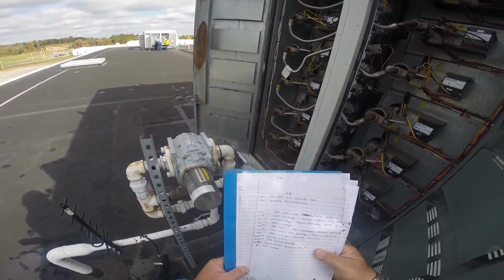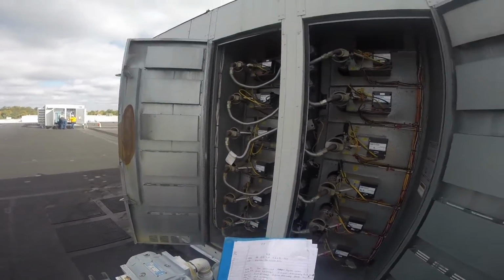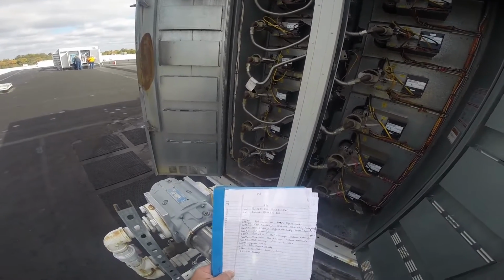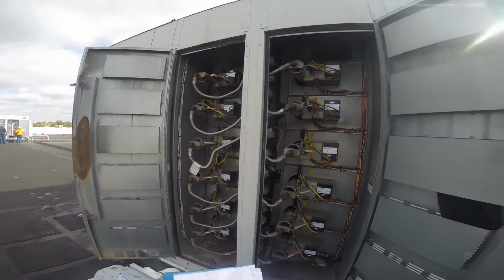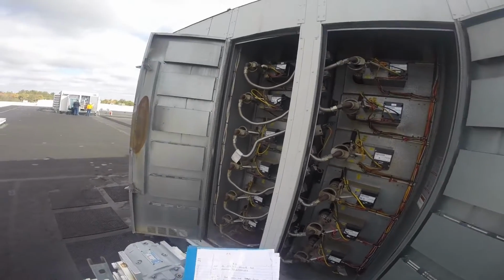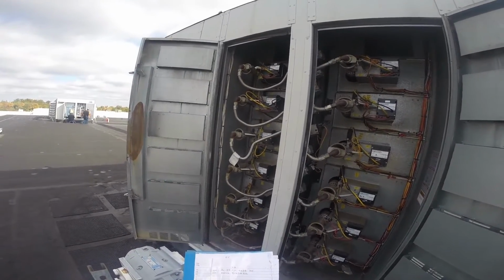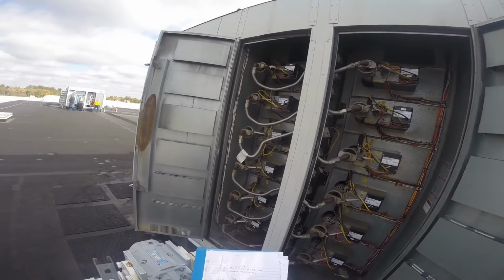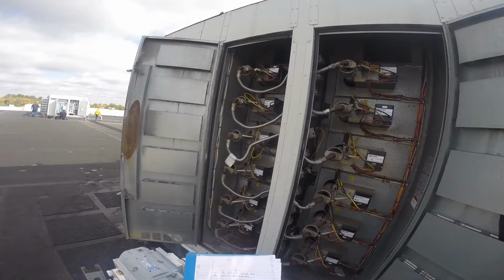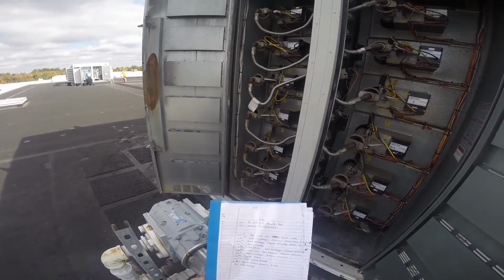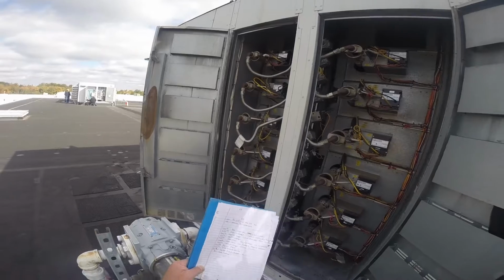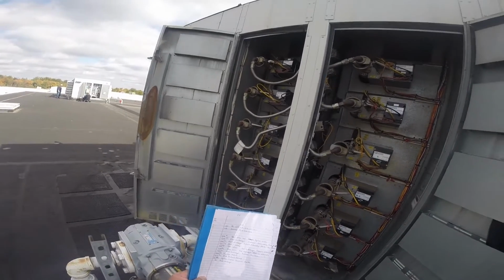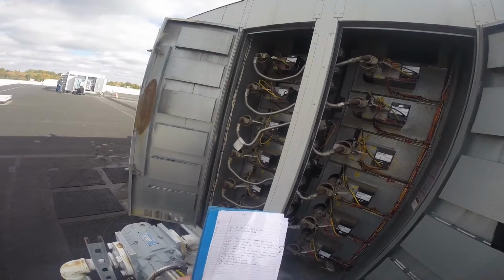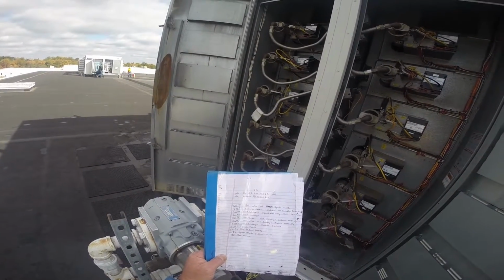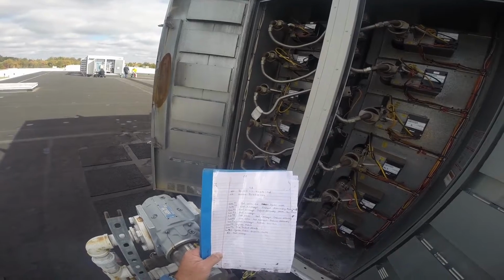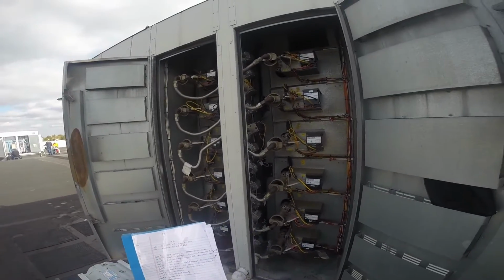We've got burner number 1. We know we've got a bad gas valve. They all need ignition wires. We don't really have the vacuum that we should have. We never physically found a hole in a heat exchanger, but we don't have the proper airflow either. Pretty sure the heat exchanger on number 2 is bad. It's going to need a new inducer motor assembly. Number 3, it's also going to need an induced draft motor.